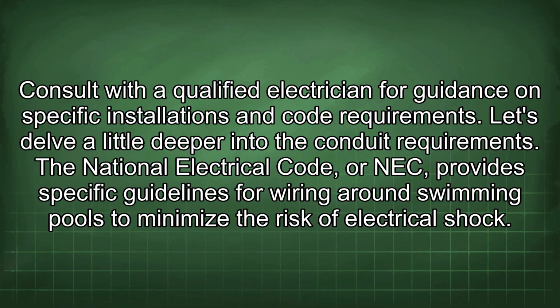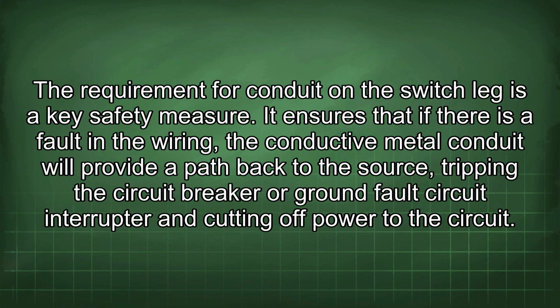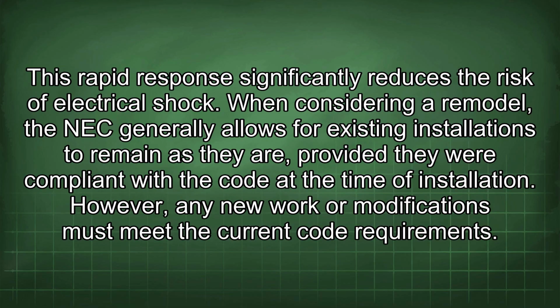The National Electrical Code, or NEC, provides specific guidelines for wiring around swimming pools to minimize the risk of electrical shock. The requirement for conduit on the switch leg is a key safety measure. It ensures that if there's a fault in the wiring, the conductive metal conduit will provide a path back to the source, tripping the circuit breaker or ground fault circuit interrupter and cutting off power to the circuit. This rapid response significantly reduces the risk of electrical shock.